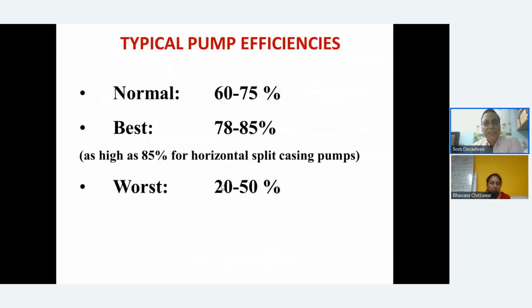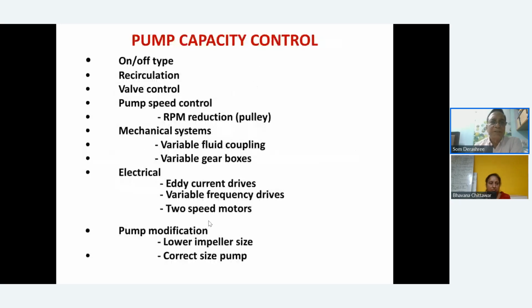Typical pump efficiencies: 60 to 75% is normal, but if you are maintaining all the pumps, motors, couplings, lubrication and vibrations very well, everything is fine, and 78 to 85%, up to 85%, is possible. And the worst case, which is what you normally find in old plants that are not very careful about their pumps, is efficiencies only in the range of 20 to 50%.